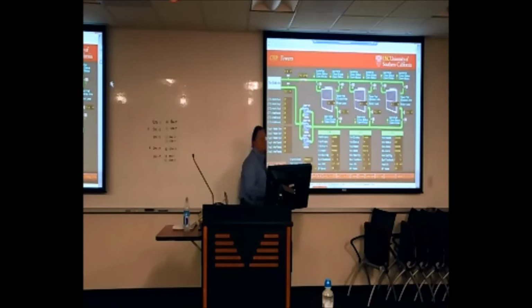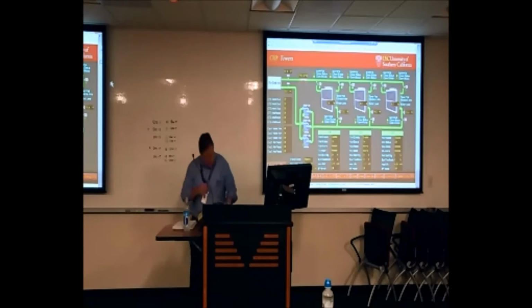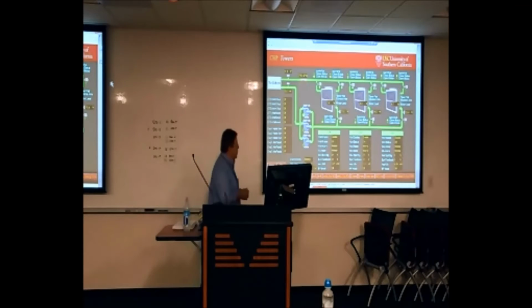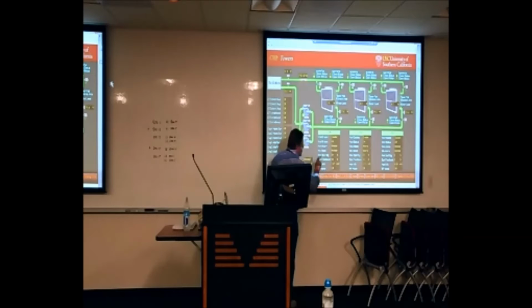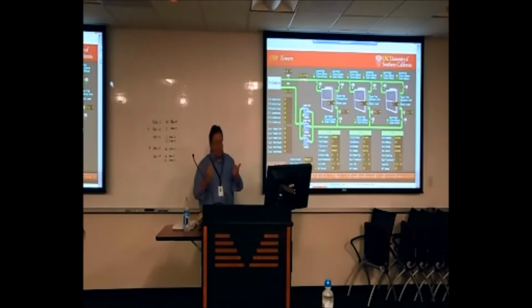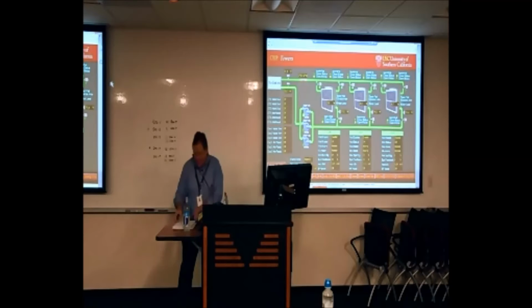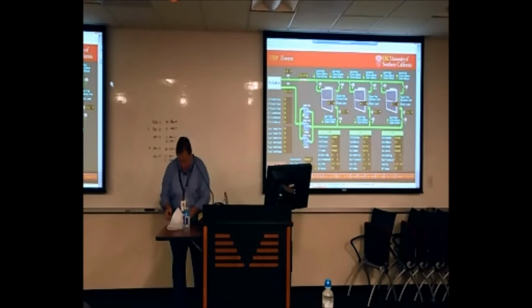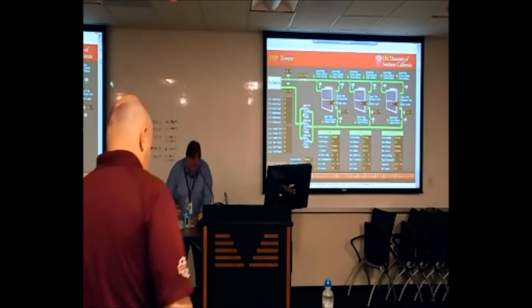Now, does that have anything to do with the failure? Does it see the status, or is it going to throw us into a failure mode? That I don't remember, Craig, and I need to find it out. If you went to bypass, we might not see the status. You know what? I think in the software I took that into account. If we're in bypass, I think I use that status along with the other status, allowing the bypass status or the drive status. Let me confirm and I'll get back to you on that. Let me make a quick note. I kind of remembered having the bypass status in there, though.